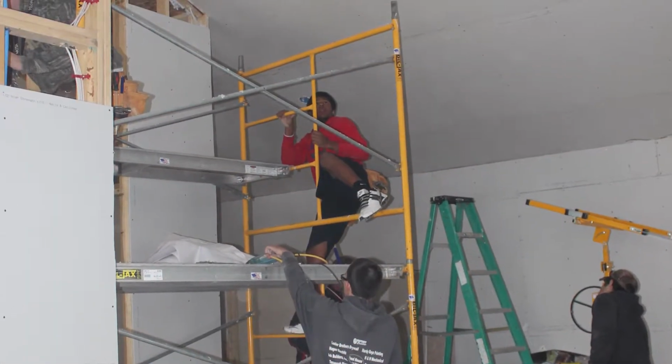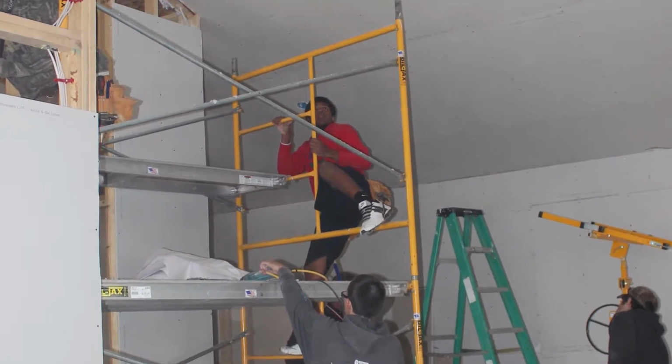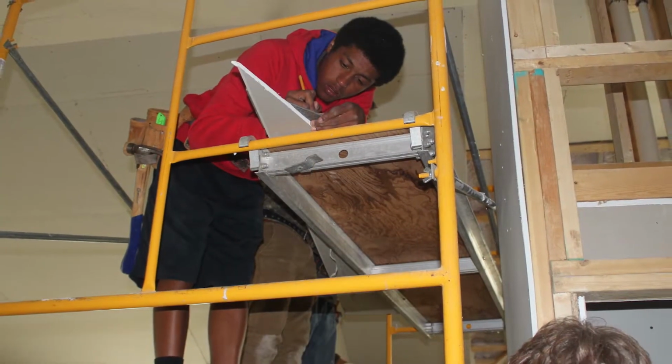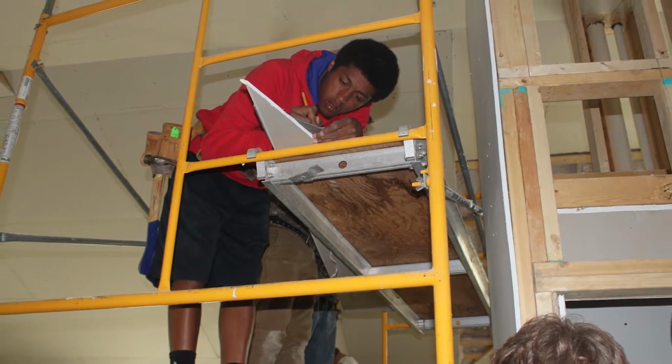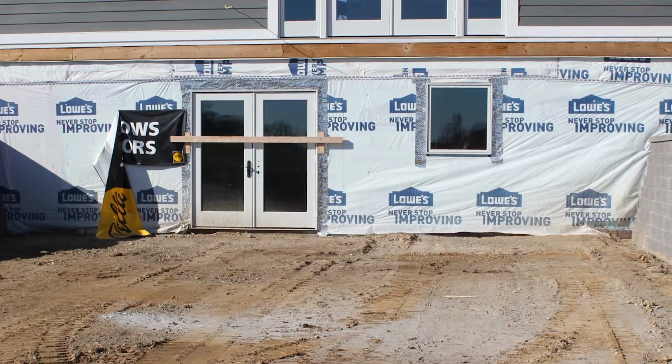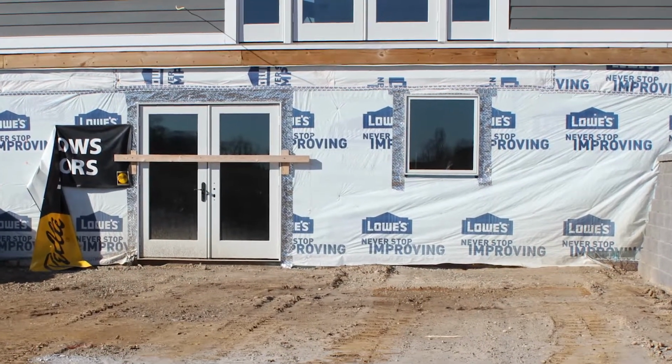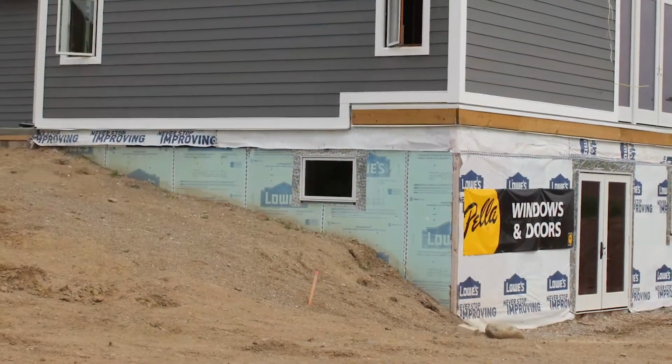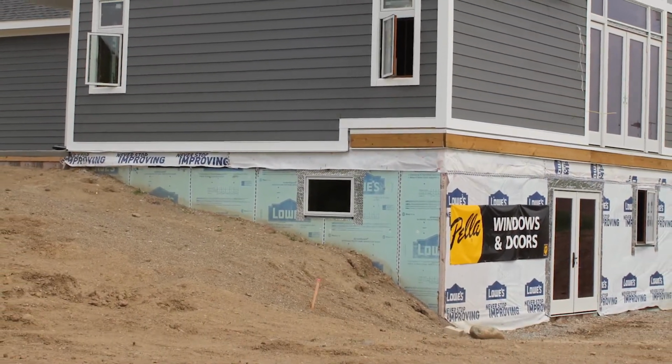As we decrease infiltration and increase insulation levels of our walls, we cannot overlook durability. Our tighter walls are much more susceptible to moisture. Walls have a continuous flashed drainage layer on the exterior, with importance placed on it being continuous and uninterrupted to ensure bulk moisture from rain and snow does not penetrate the wall assembly. Additionally, walls with an adequate level of continuous exterior insulation will reduce the potential for condensation on the interior of the wall.